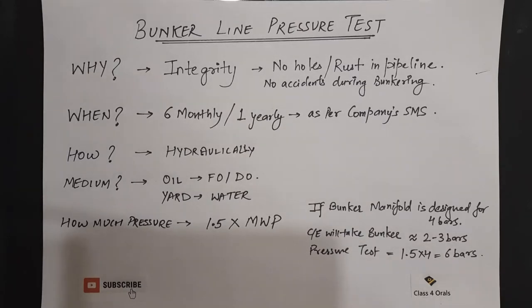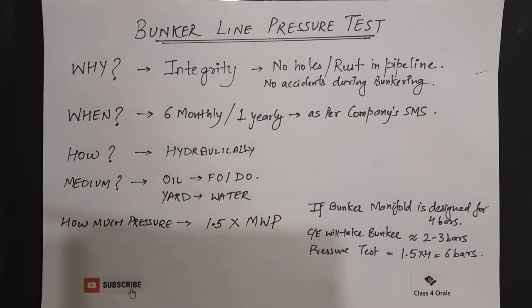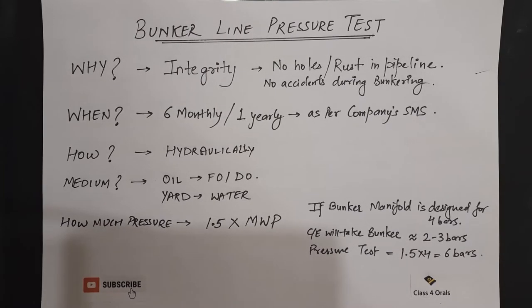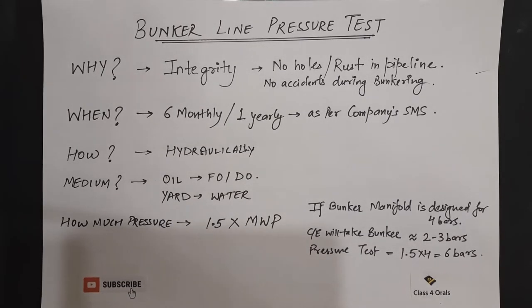When do we conduct the bunker line pressure test? The bunker line pressure test is conducted 6 monthly or 1 yearly as per the company's SMS. How do we conduct it? It is conducted hydraulically. What is the medium? It is either oil, fuel oil or diesel oil. And in yard, it is conducted by water.